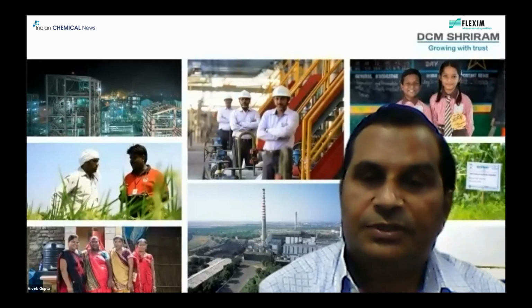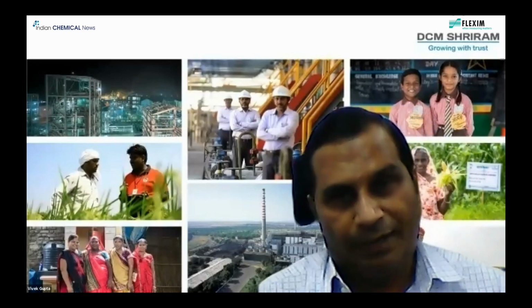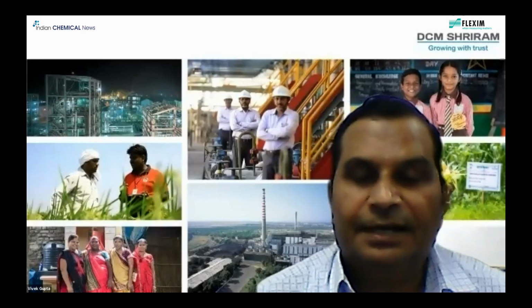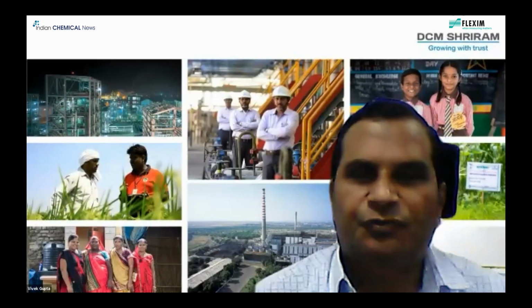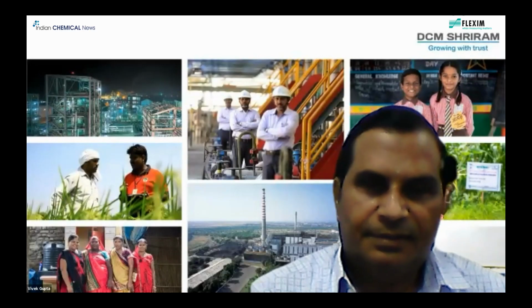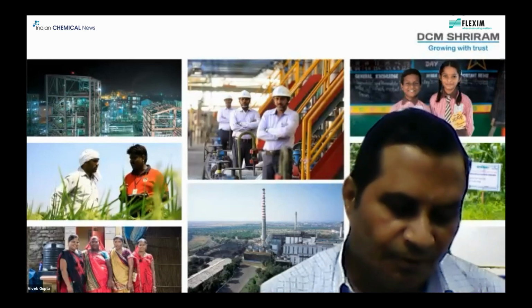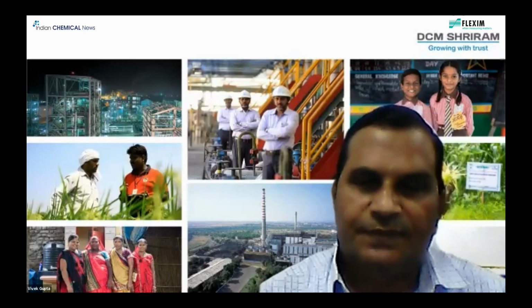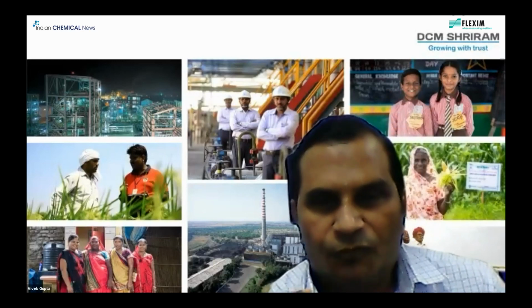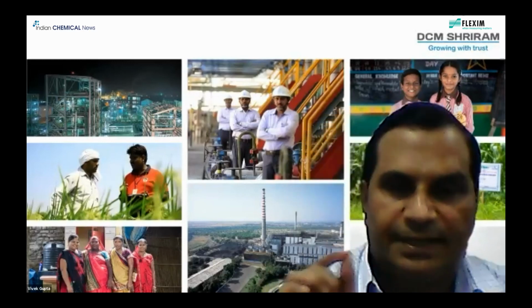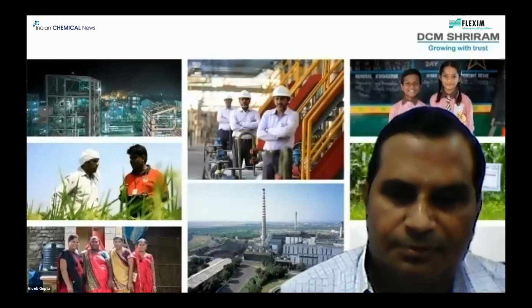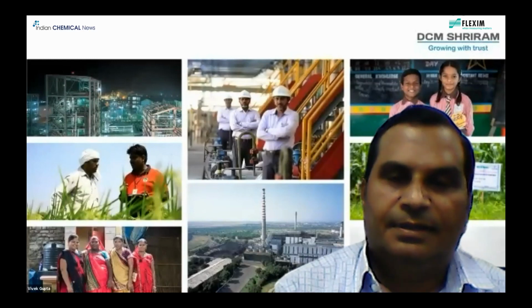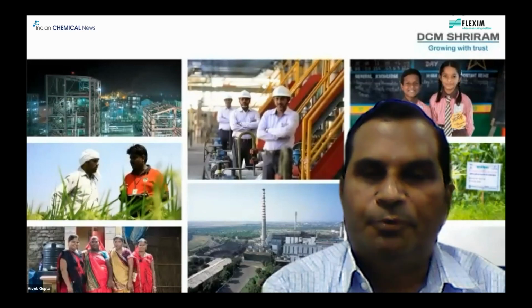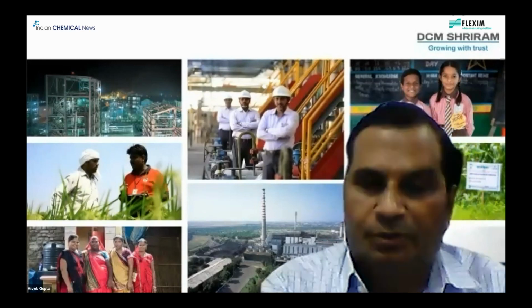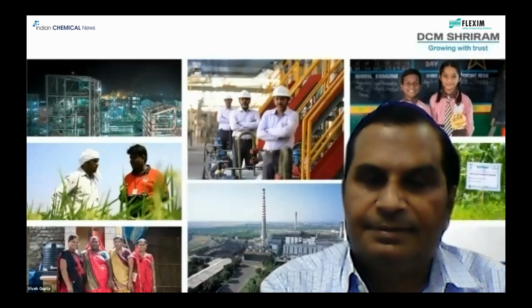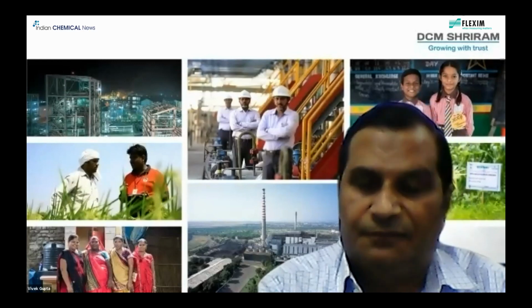The other two applications which I am going to share are lubricating oil for cooling, and that pipeline is very small, only a 3x4 inch pipeline, which we commissioned only yesterday. Once we talk about a flow meter, we think of 4 to 20 milliamps output, which we take to DCS. But this particular clamp-on meter which we have installed has a digital output also, and the indication is available in the field itself.